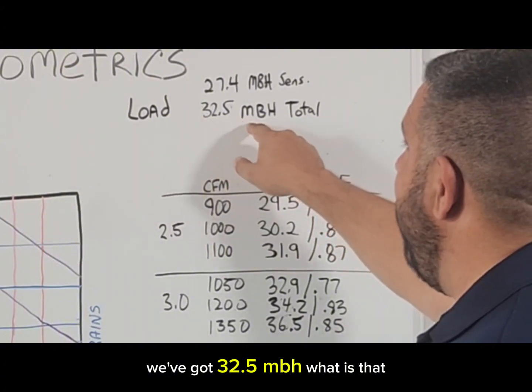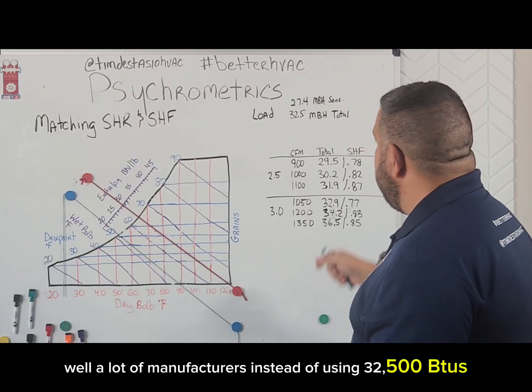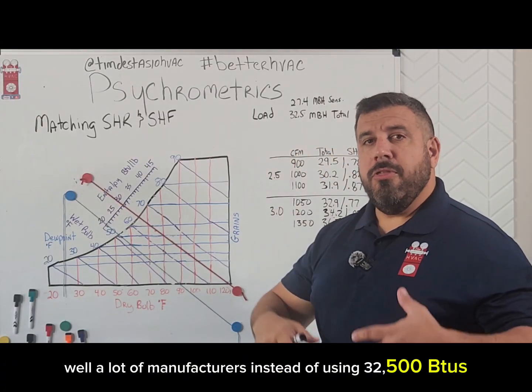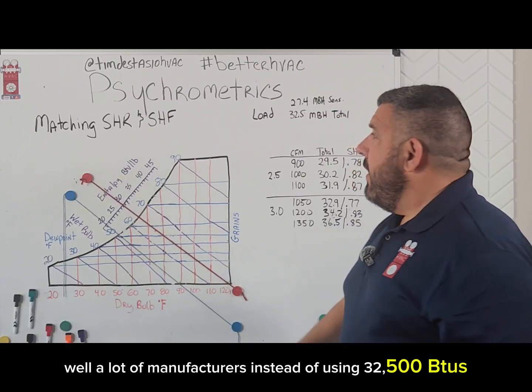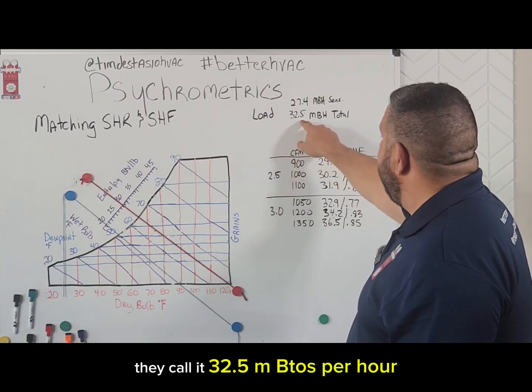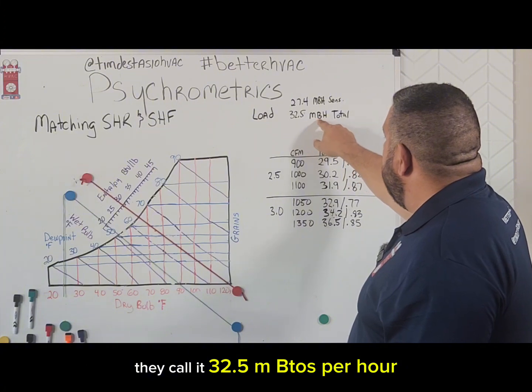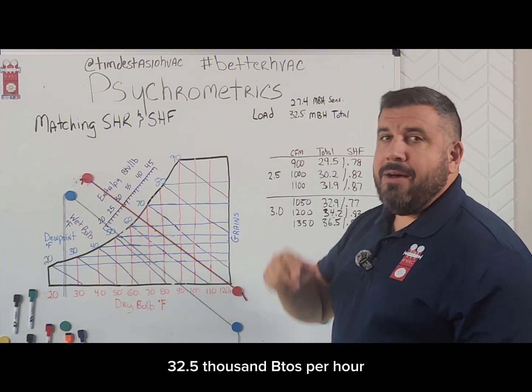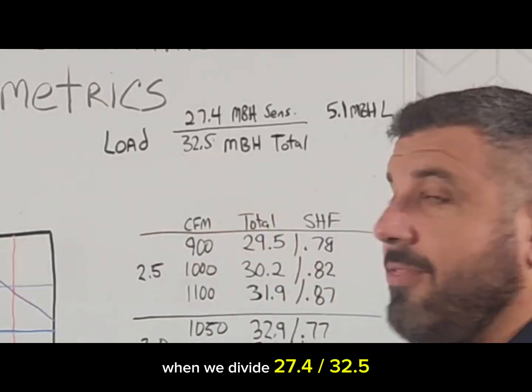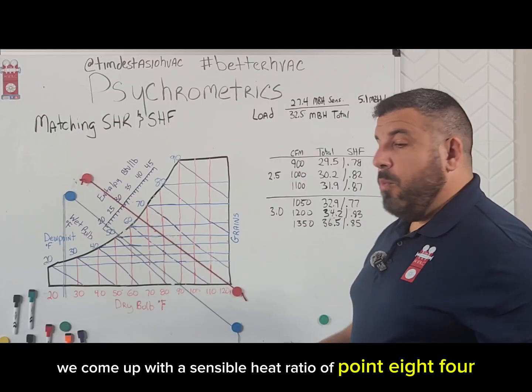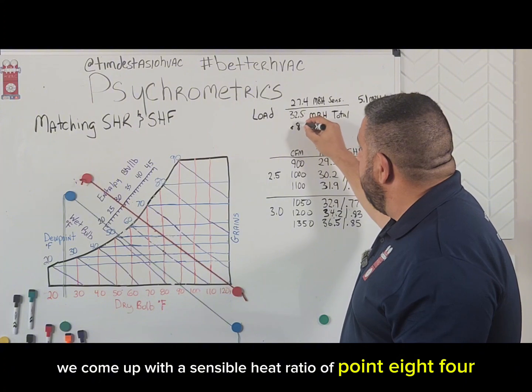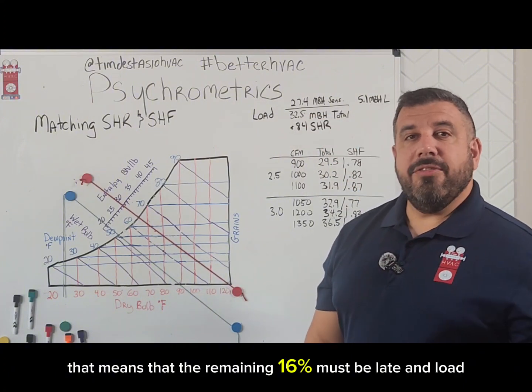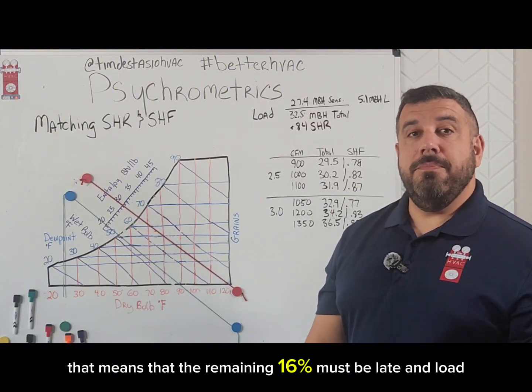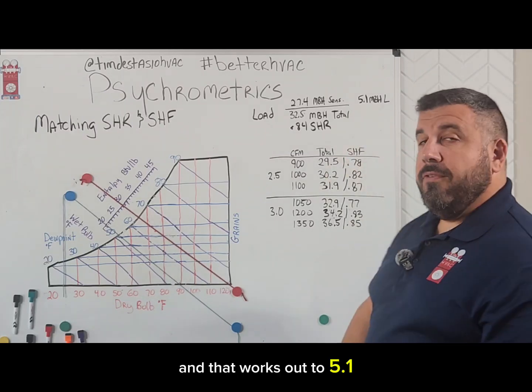Out of our load calculation, we've got 32.5 MBH. Well, what is that? A lot of manufacturers, instead of using 32,500 BTUs, call it 32.5 MBTUs per hour, 32.5 thousand BTUs per hour. When we divide 27.4 by 32.5, we come up with a sensible heat ratio of 0.84. That means that the remaining 16% must be latent load, and that works out to 5.1.